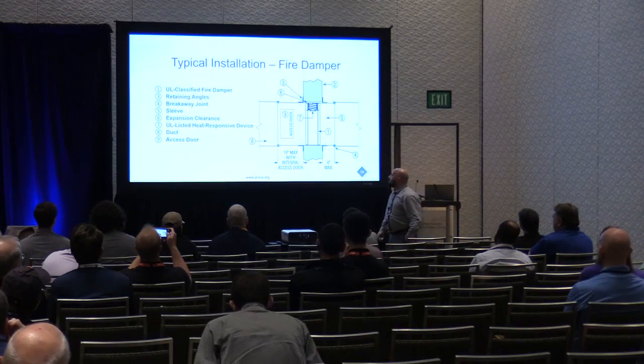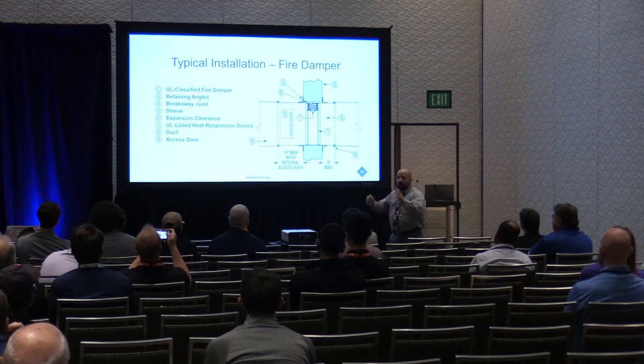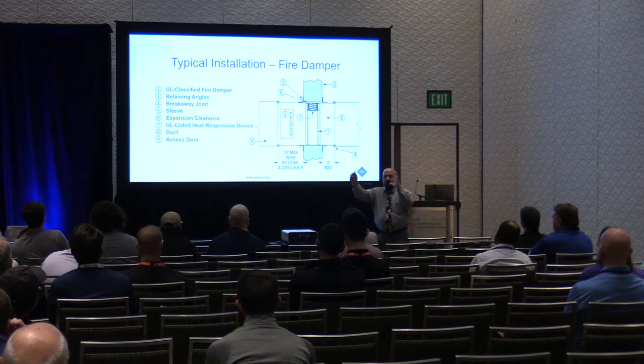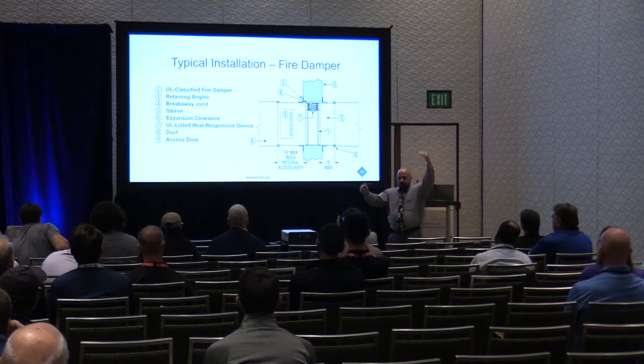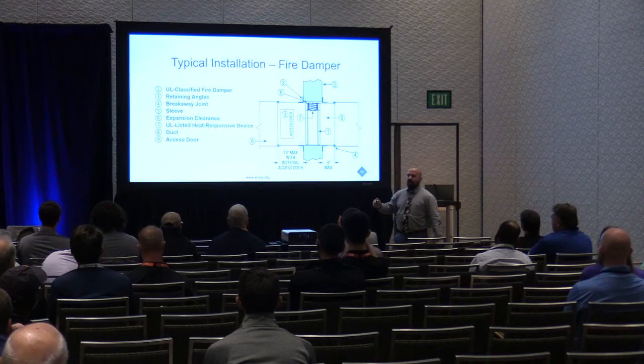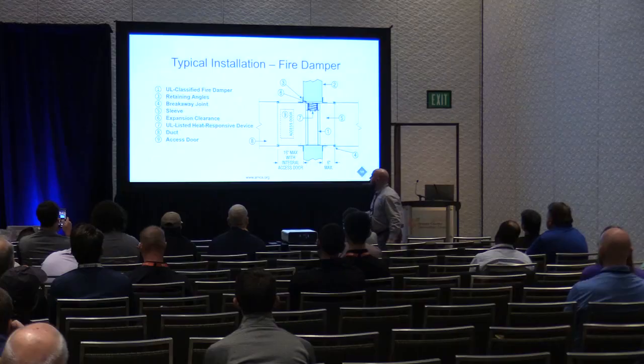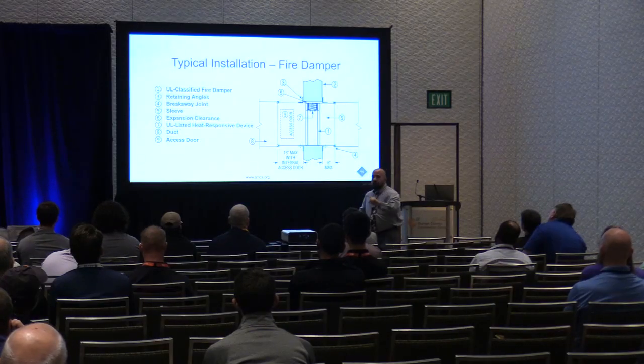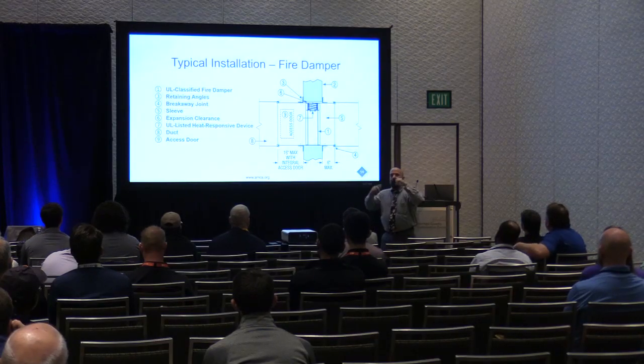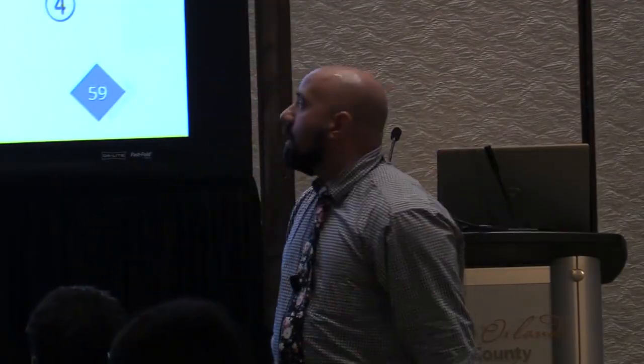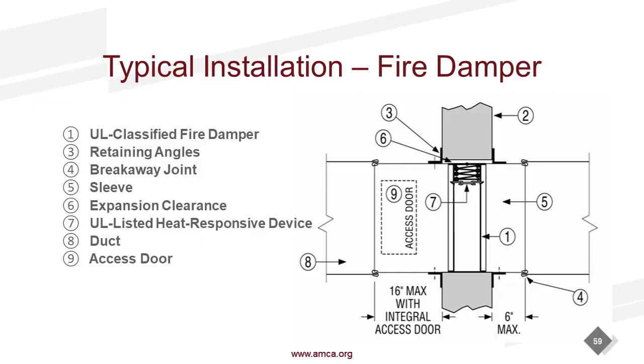Right? That is a slip and drive joint that allows the damper and its sleeve to stay in the wall, and then your mating ductwork to break away in the event of things falling out of the fire. And that retaining angle could be on one side of the damper, on both sides, and again, it's retaining the damper from falling out of the wall. If you don't pass that test in UL, you don't get your certification for your damper.